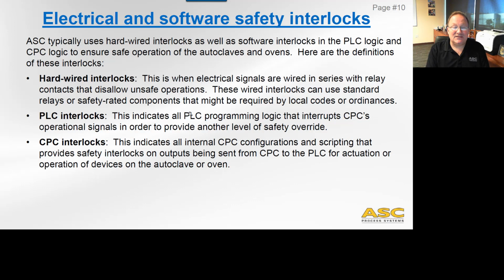PLC interlocks are basically PLC logic. So PLC programming logic that interrupts the CPC operational signal and provides a level of interlock on those signals to make sure that those don't get all the way over to the device that we're trying to control. And then there's the CPC interlocks, which is basically internal configuration and scripting that provides the safety interlocks on the outputs from CPC. So those are the different levels, and the most critical would be the hardwired interlock, because that's the last in the line. And then we have PLC interlocks and then CPC interlocks.